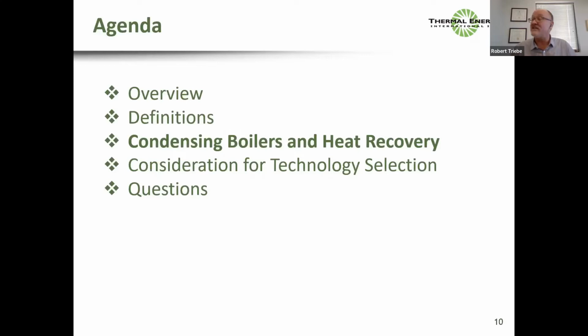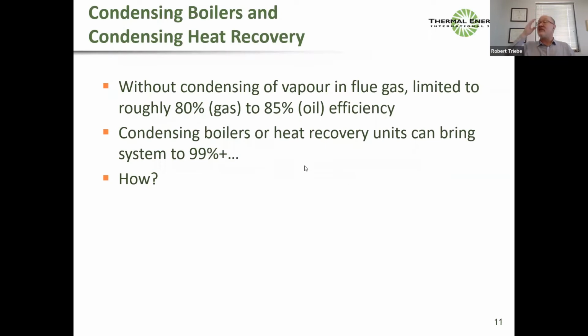Now I'm going to talk technologies a little bit, and I'm going to talk just about a few slides on condensing boilers and condensing heat recovery technologies and the basic types. So without condensing of vapors, why are we doing this? As I've mentioned, without condensing of vapors in the flue gas, we're limited to roughly 80% efficiency in a gas boiler, because a gas boiler has more water in the exhaust, and about 85% efficiency in an oil boiler. But condensing boilers or condensing heat recovery units can bring system efficiencies to 99% plus. And I'm going to give an example later that you can even be over 100% on higher heating value.